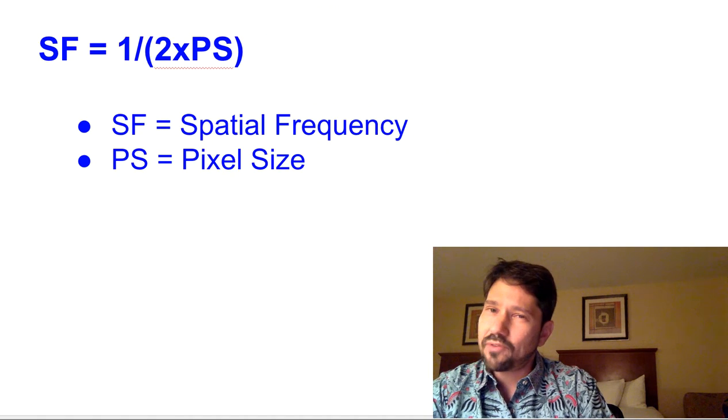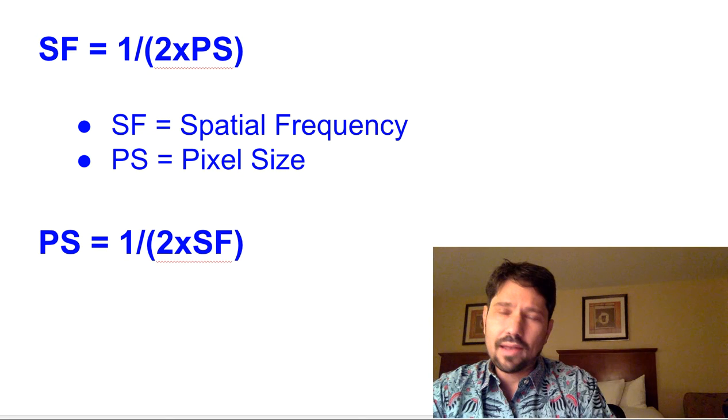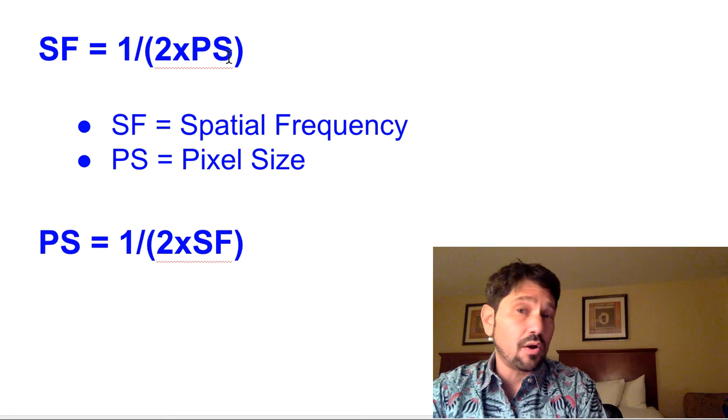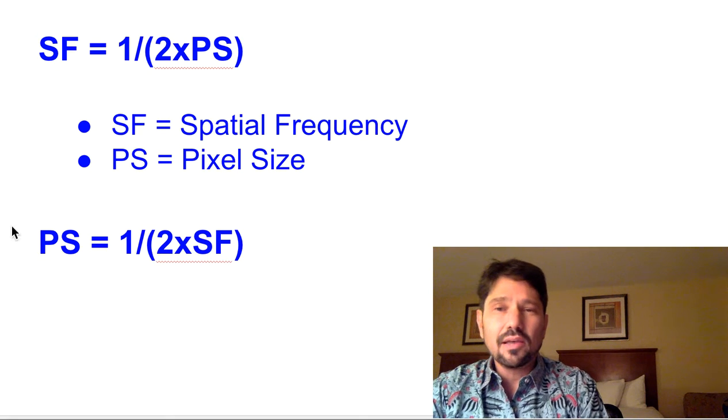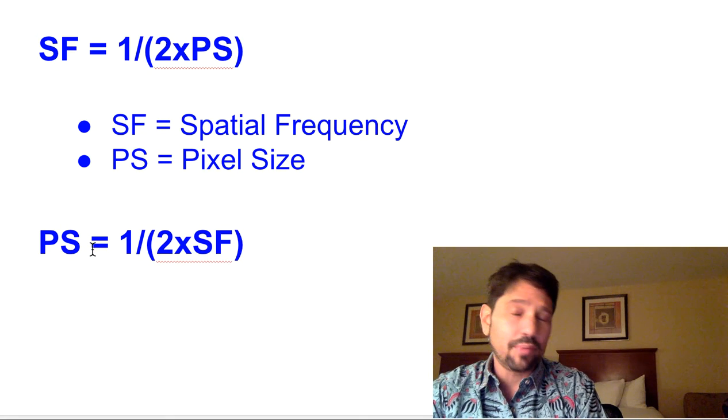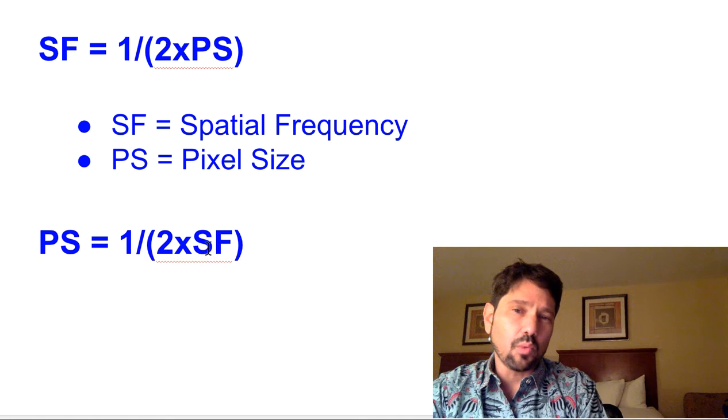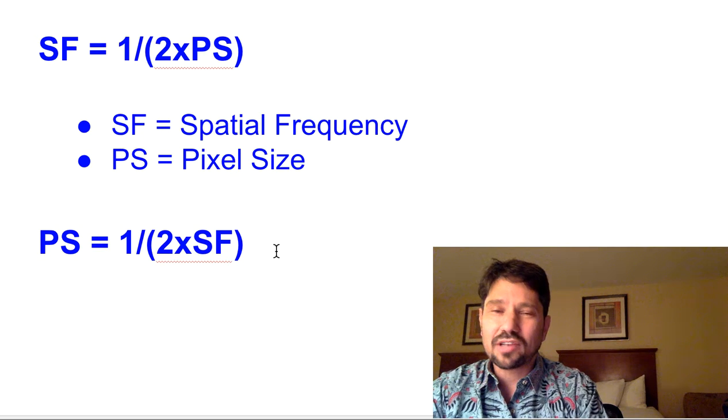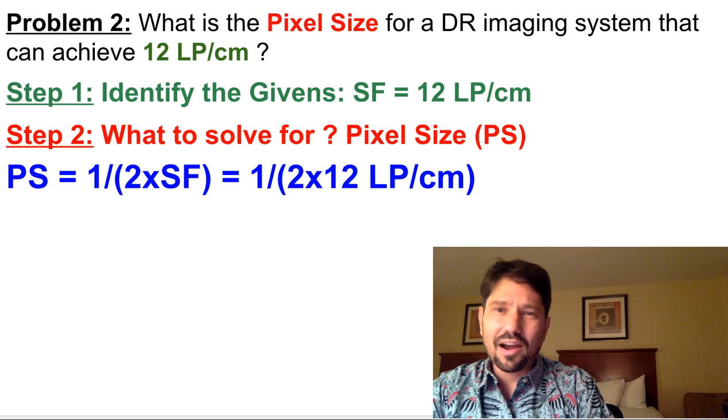So, again, we know our formula, and now we've got to be able to convert. All right, our formula said spatial frequency is 1 over 2 times pixel size. You'll need to do some algebra to be able to say, well, pixel size then must equal 1 over 2 times spatial frequency. I will leave that algebra as an exercise for the student.